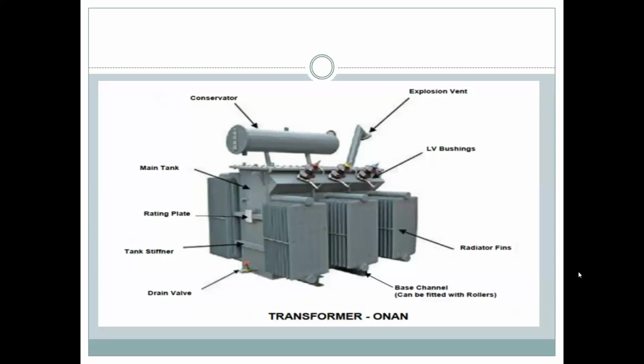Now this is also an important thing: once pressure develops inside the transformer, there is a membrane, aluminum foil or something like that, which, if the pressure goes more than 5 psi, gets ruptured and the extra pressure oil comes out. Once it gets ruptured, the transformer has to be taken out of service again to put that membrane back.